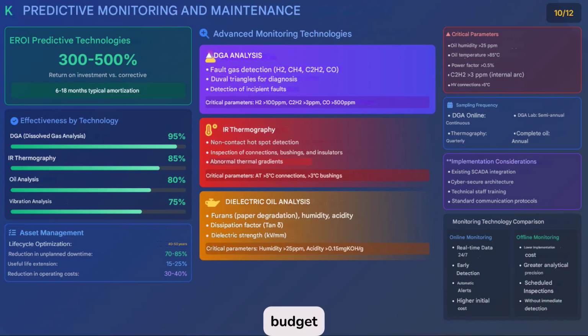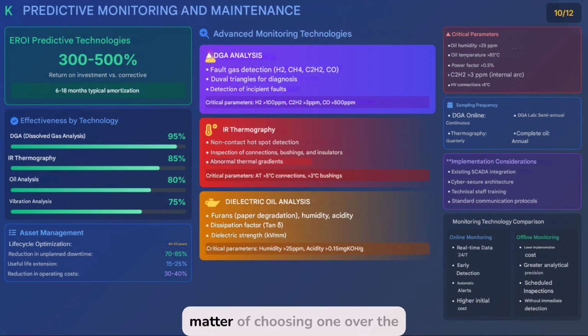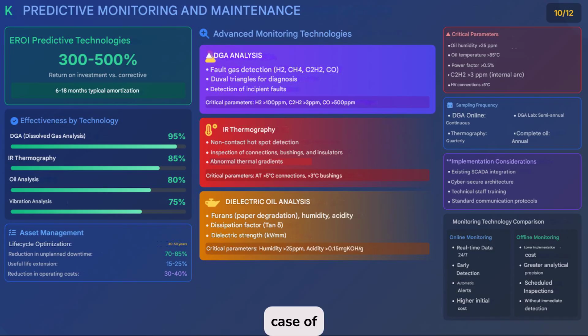minimize budget uncertainty. When asked which technologies offer the greatest impact, dissolved gas analysis, DGA, stands out with an effectiveness rate of 95%, closely followed by infrared thermography, 85%, dielectric oil analysis, 80%, and vibration analysis, 75%. However, it's not a matter of choosing one over the other, because these tools don't compete with each other. They complement each other. The true value emerges when they are integrated into a comprehensive early diagnosis system that allows intervention priorities to be established, resources to be allocated intelligently, and the margins of error to be reduced in operational decision-making. Take the case of DGA.